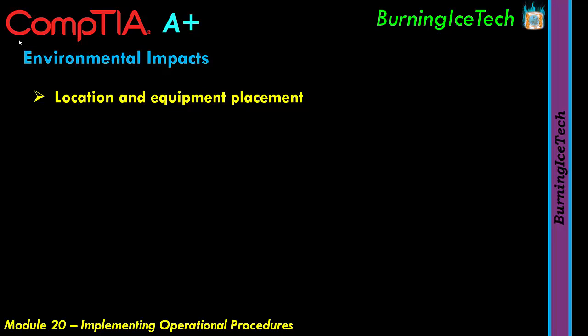But this server room had windows, and they were facing west. Every afternoon after lunchtime, the sun would start shining through these windows, making the server room hotter than it should be, and it was shining directly on the back of the servers at least, which means the servers get hotter and hotter. Ideally, we want servers to stay as cool as possible, not as hot as possible. A hot server is a server that's not going to respond to you.